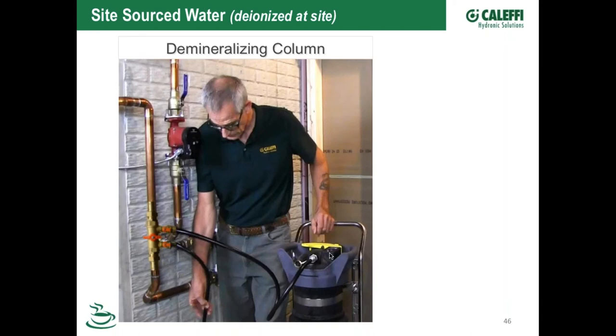So you don't want to put water that's been stripped completely of everything—get it too pure—because you won't have the conductivity. Now, what we found is even if you take the water out of here down to a low parts per million, let's say 5 parts per million, and put it in the system, within sometimes hours or within the first day, it's going to pull some of the metals, some of the brass or copper, maybe the iron body, out of the system, and it's going to buffer that number back up a little bit just from what it pulls out.